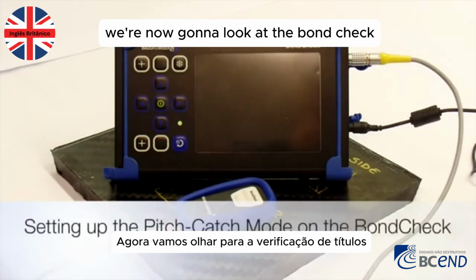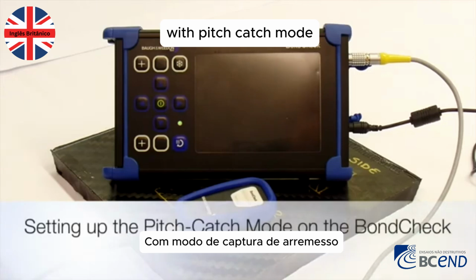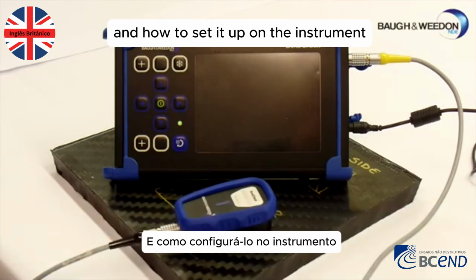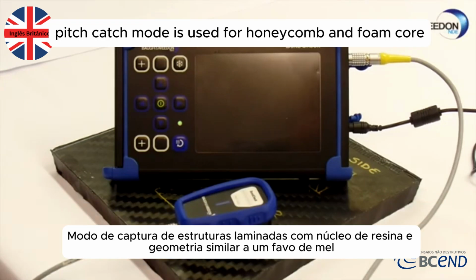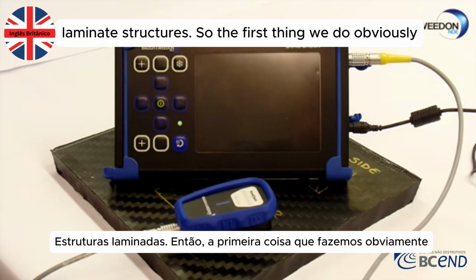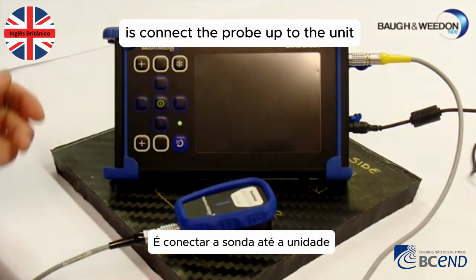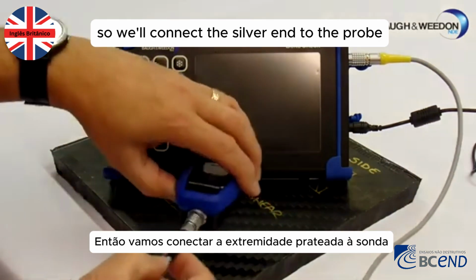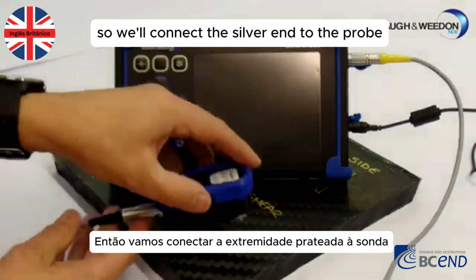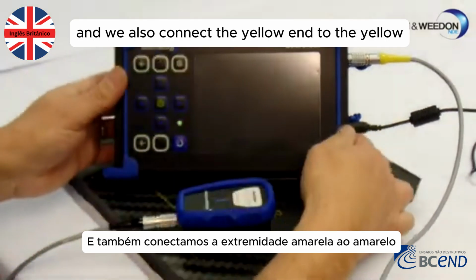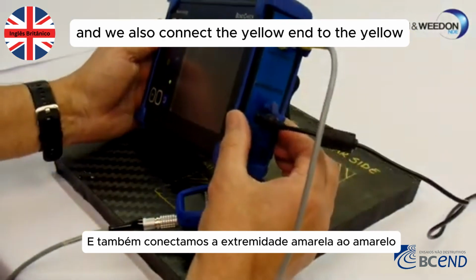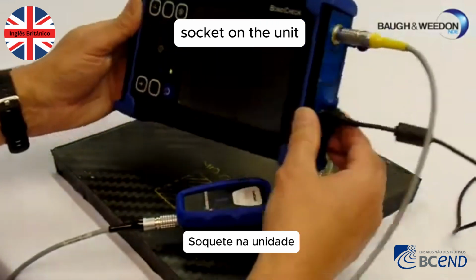We're now going to look at the bond check with pitch catch mode and how to set it up on the instrument. Pitch catch mode is used for honeycomb and foam core laminate structures. So the first thing we do obviously is connect the probe up to the unit. We'll connect the silver end to the probe, and we also connect the yellow end to the yellow socket on the unit.